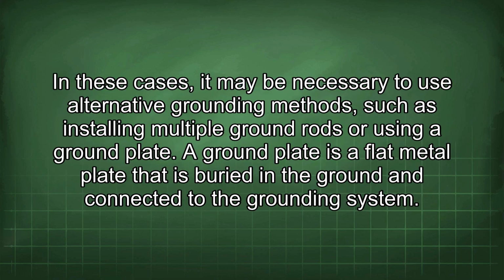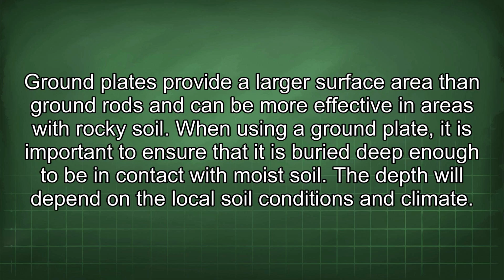In these cases, it may be necessary to use alternative grounding methods, such as installing multiple ground rods or using a ground plate. A ground plate is a flat metal plate that is buried in the ground and connected to the grounding system. Ground plates provide a larger surface area than ground rods and can be more effective in areas with rocky soil. When using a ground plate, it is important to ensure that it is buried deep enough to be in contact with moist soil. The depth will depend on the local soil conditions and climate.